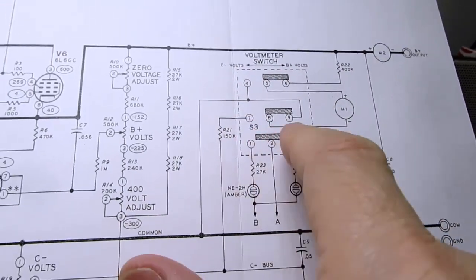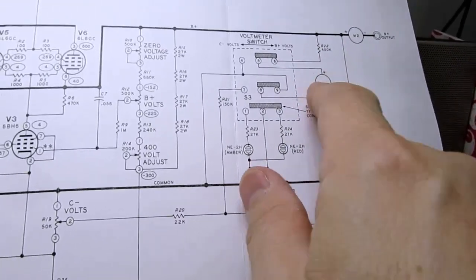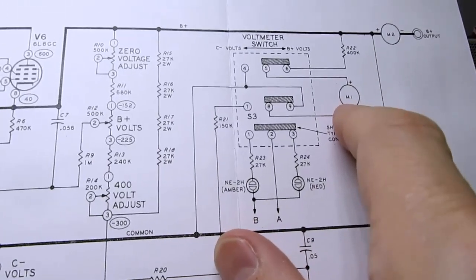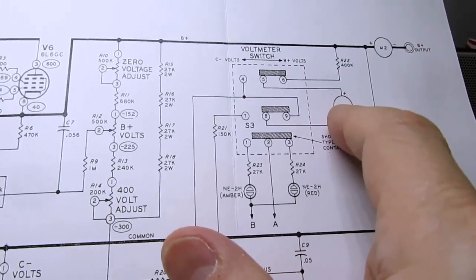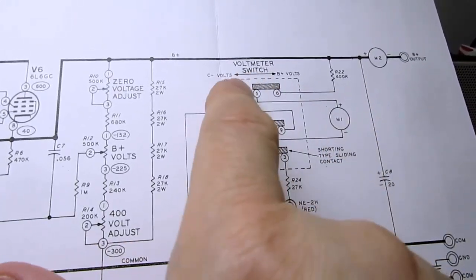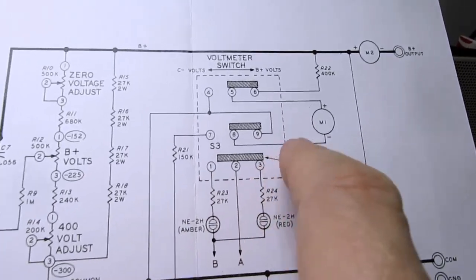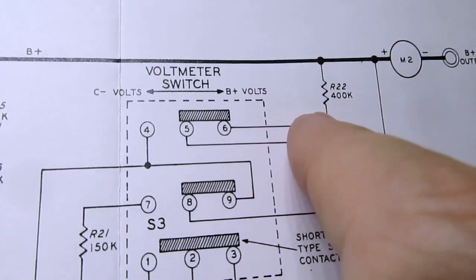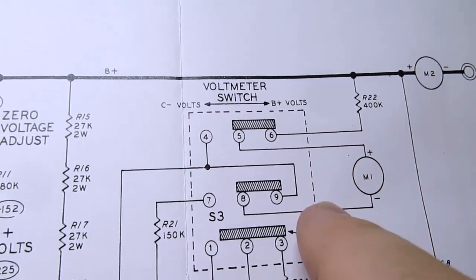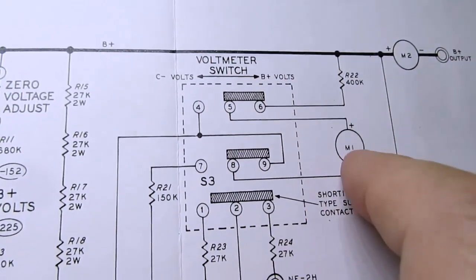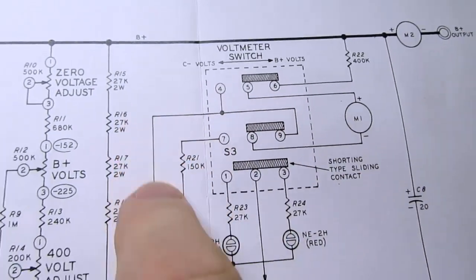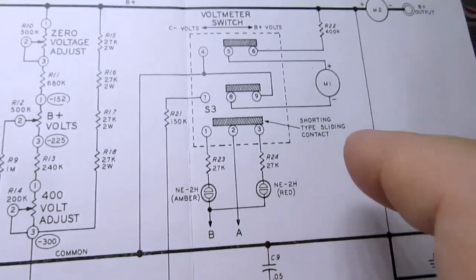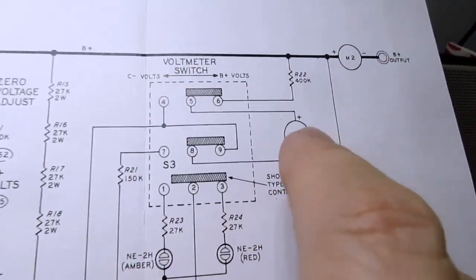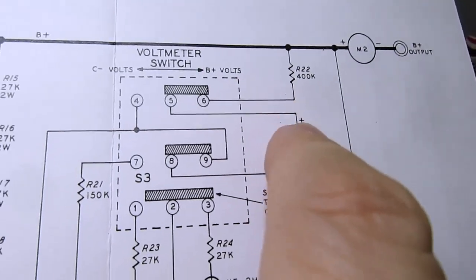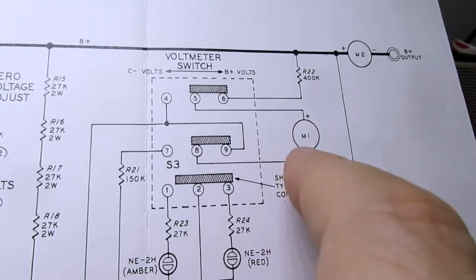This switch here on the front panel determines which of the two supplies the voltmeter is looking at. This is also a milliamp meter, and in order to make a milliamp meter work as a voltmeter, you have to have a series resistance. So when the switch is in the B volts position, the switch is over to the right here, and it connects this 400K resistor through the meter, and notice that the plus side of the meter is connected to the plus side of the supply, so the current will go through in the correct direction. And then it continues through this guy and comes back around and goes to circuit common. So the meter is put between here and here with a 470 or 400K resistor in series with it, so it gives the proper span.